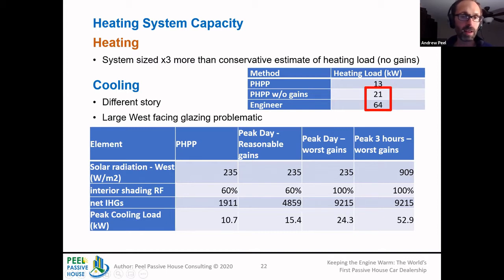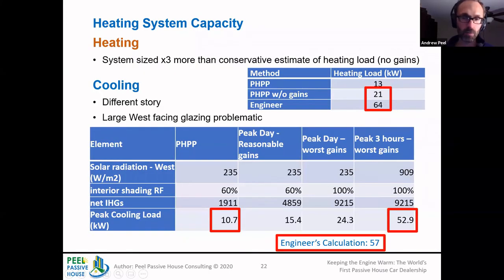So we looked at our peak day with more gains than PHPP usually assumes. We even looked at the peak day with the worst amount of gains, like all the equipment on, the most number of customers and staff they'd have at one time, all the lights on. And then we took the worst three hours of the day, where we get the most sun coming from the west side as well. And you can see the factor of five difference in the load. In the end, that calculation was closer to the engineer's calculations. So this was a case where we couldn't confidently or reasonably argue to downsize the equipment. It came back to the killer west glazing, which put too much of a solar load on the building to be able to reduce the system size.